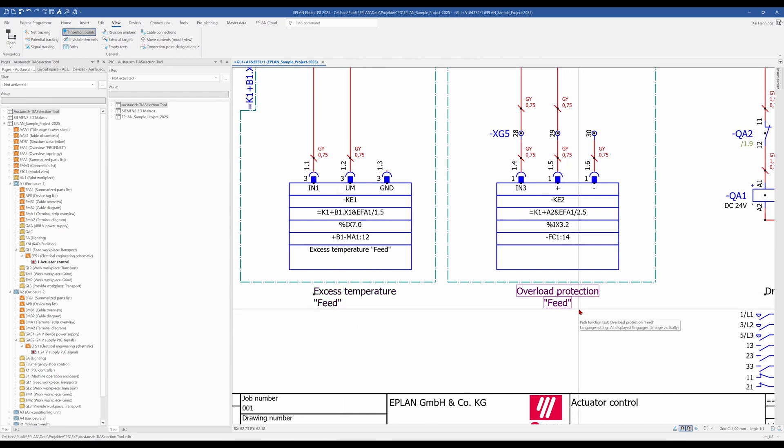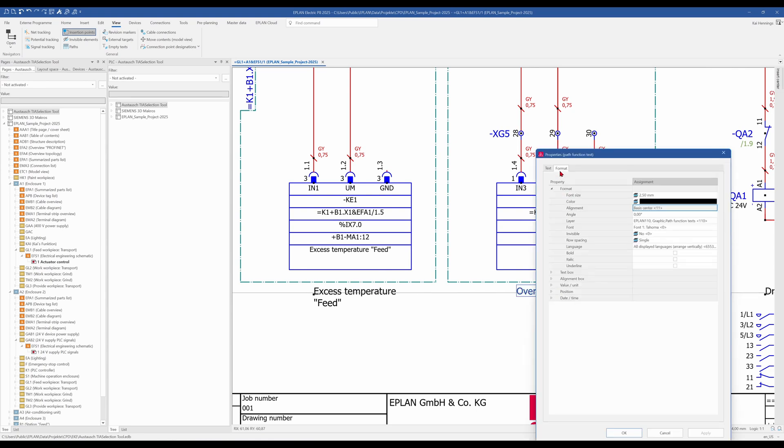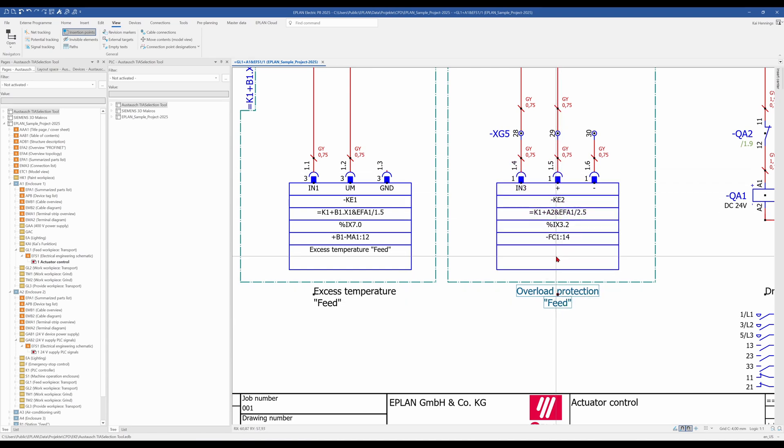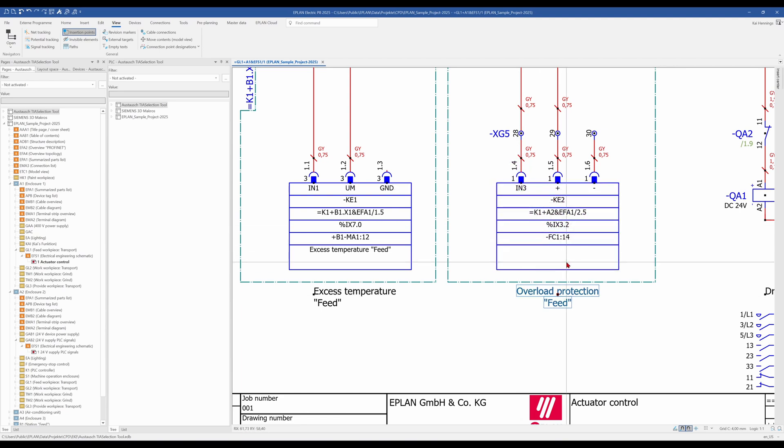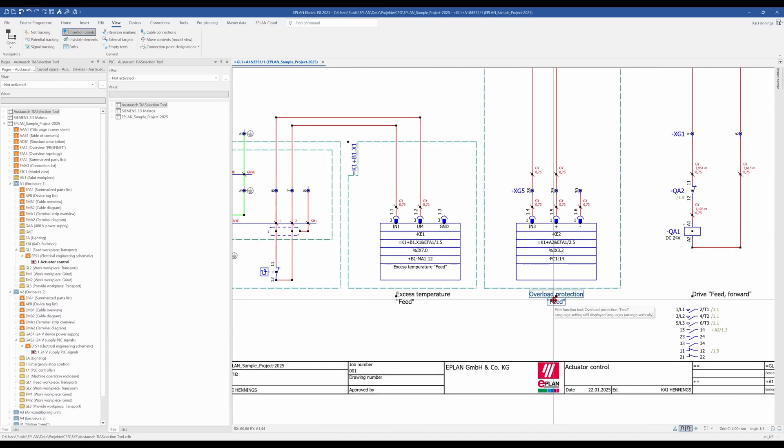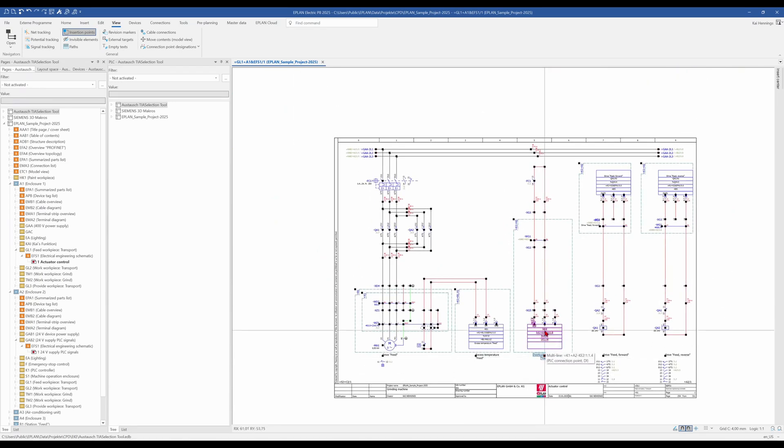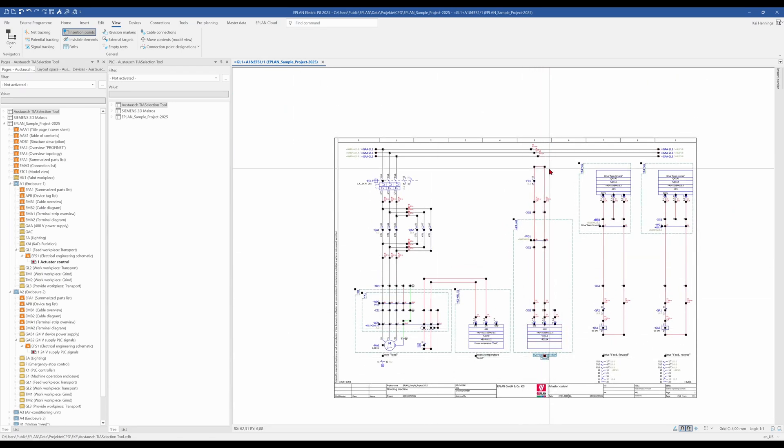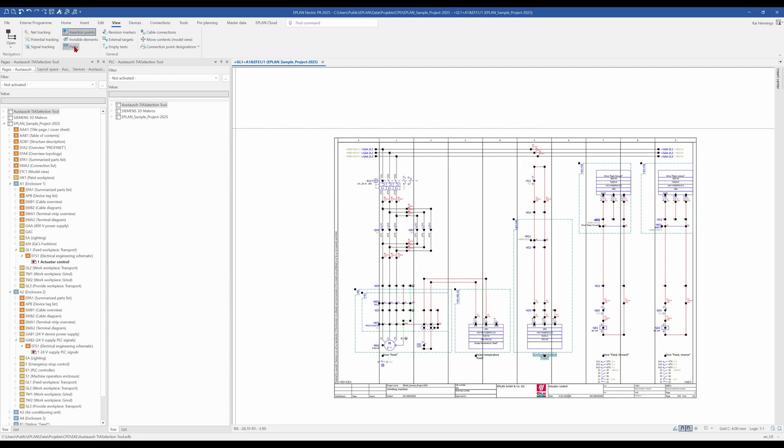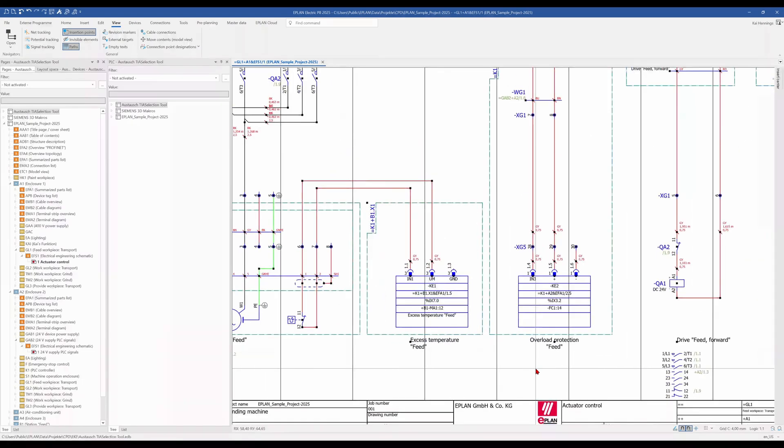For a little bit better view or if you like the design a little bit more you want to have it like here as a basic center function text. So you can make the setting here at format and basic center and want to have it centered below the PLC box. And that means that you will not get the function text here. The result is also that you will not get the function text on the PLC overview page. But there is a solution in EPLAN as long as your text and the PLC box or cable or whatever is in one path. So first of all I go to view and make the path areas visible.